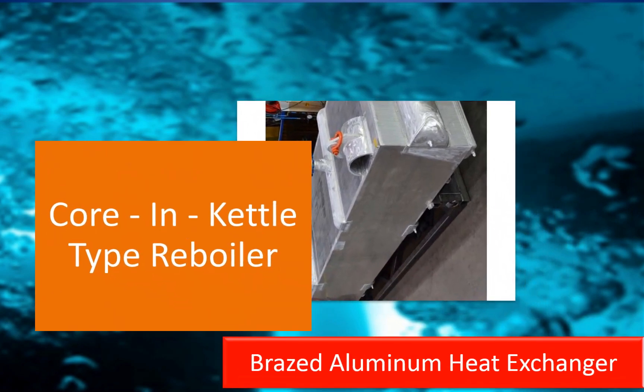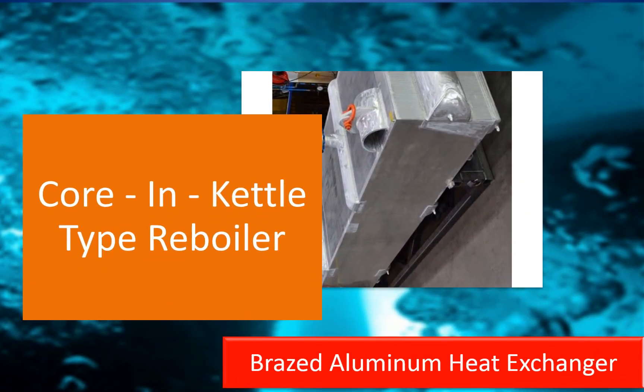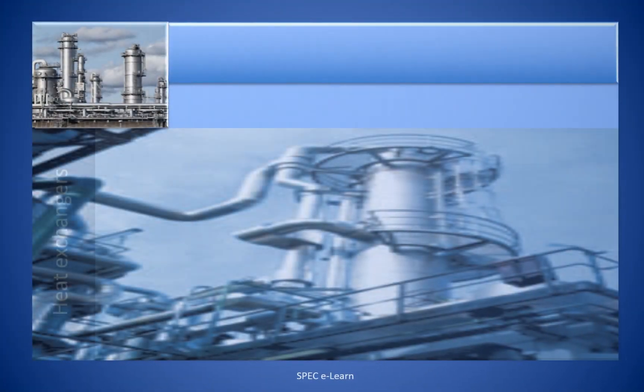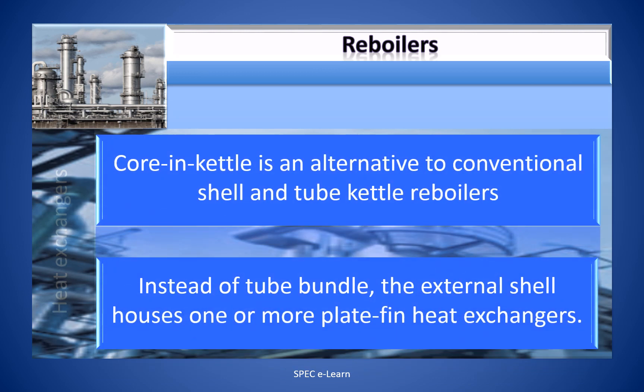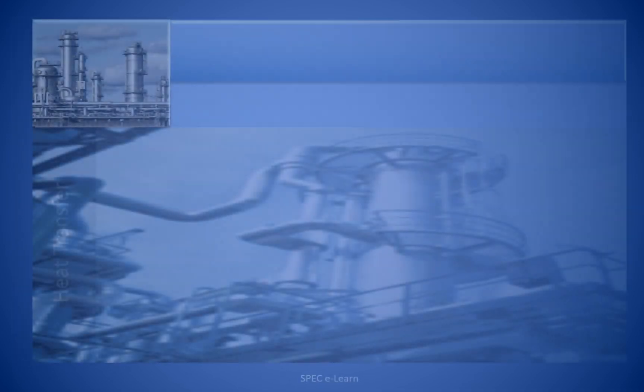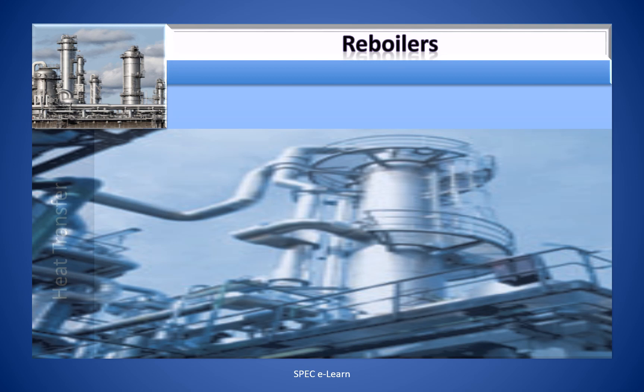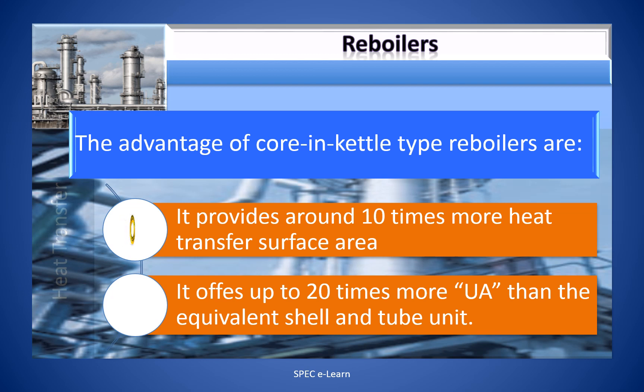Now let me introduce you to the most innovative and advanced reboiler technology: the core in kettle type reboiler. Core in kettle is an alternative to conventional shell and tube kettle type reboilers. Instead of a tube bundle, the external shell houses one or more plate fin heat exchangers. It provides around 10 times more heat transfer surface area compared to a conventional shell and tube kettle type reboiler, and offers up to 20 times more UA than the equivalent shell and tube unit.